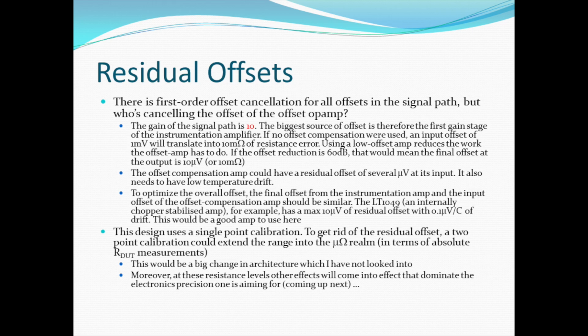Since I use a single point calibration, that's how the entire instrument was designed. I didn't want to have to deal with calibration at 2 points. I said, okay, let me calibrate at one known point, and then because of the offset cancellation loop, it should theoretically be zero at zero resistance, but of course that's not going to be true. So that sets a limit. Any residual offset limits the minimum value of resistance that you can actually measure.